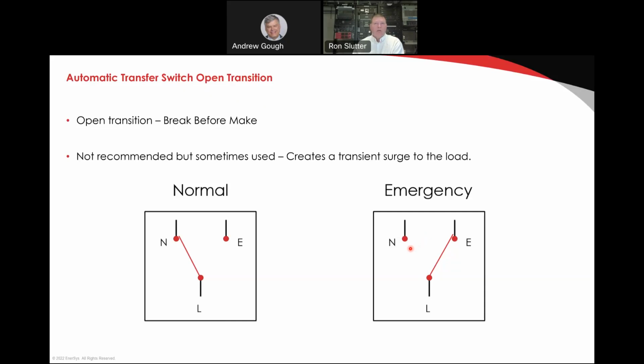This certainly will work. What equipment gets affected when we're in a telecommunications facility when we do this operation? Our rectifiers and our DC plant and our inverters, which are taking the brunt of these transients because those are pieces of equipment that are in the protection circuit to protect the downstream loads, whether they be DC or whether they be AC, right? So that's the equipment that's going to get those. So if you're losing rectifiers or inverters in your telecommunications facility, there are some reasons why that may be happening, and this is one of them. You have an open transition ATS. All right, let's move on.